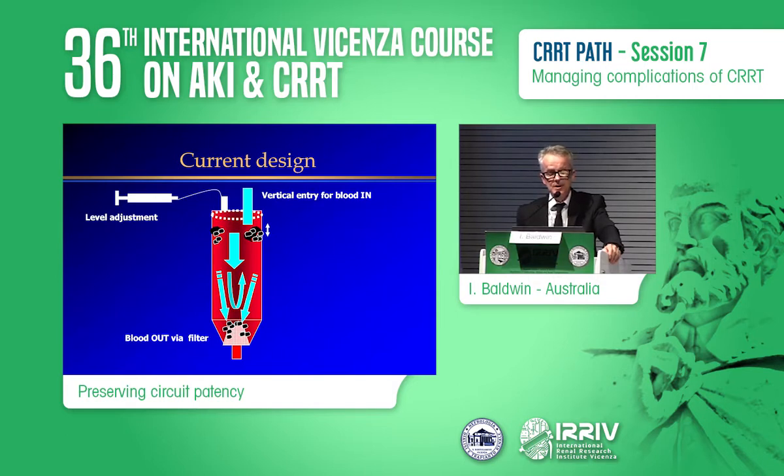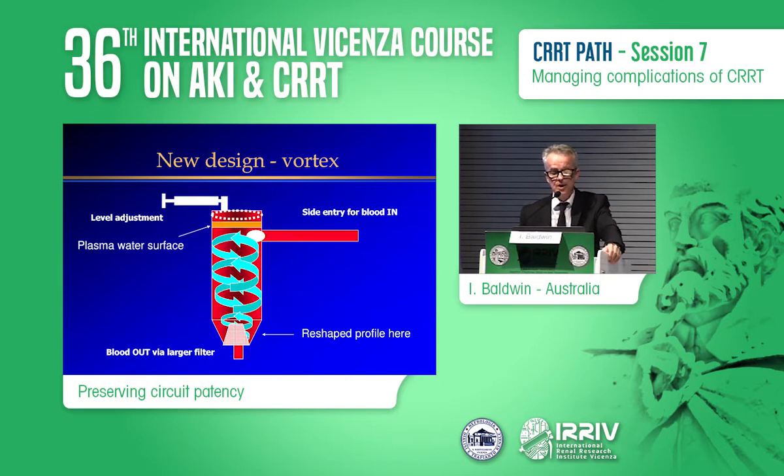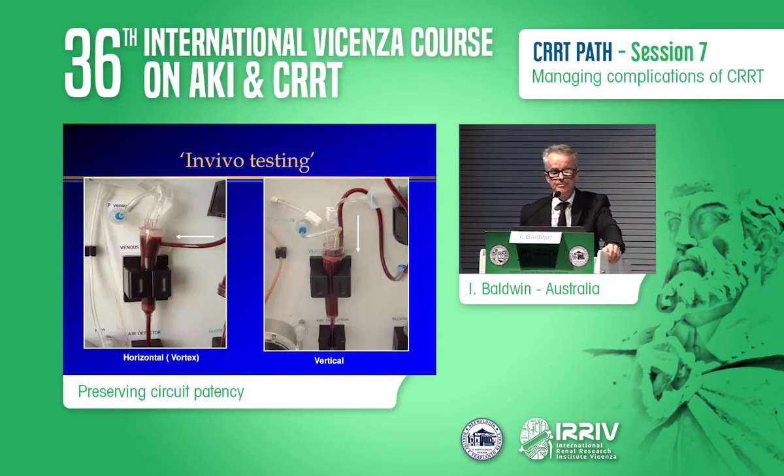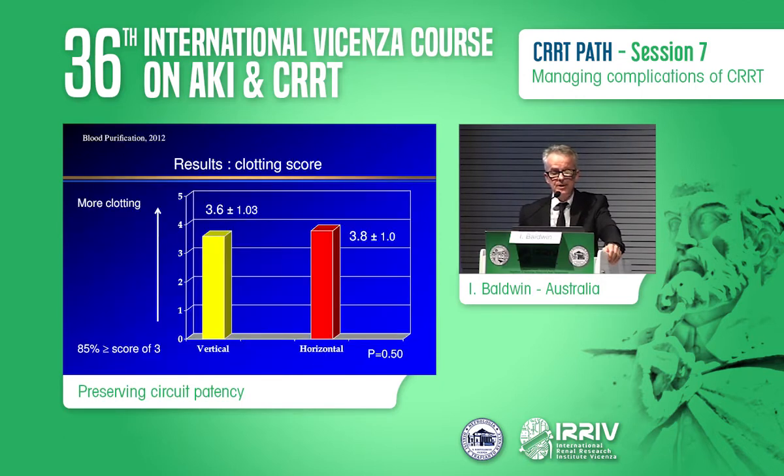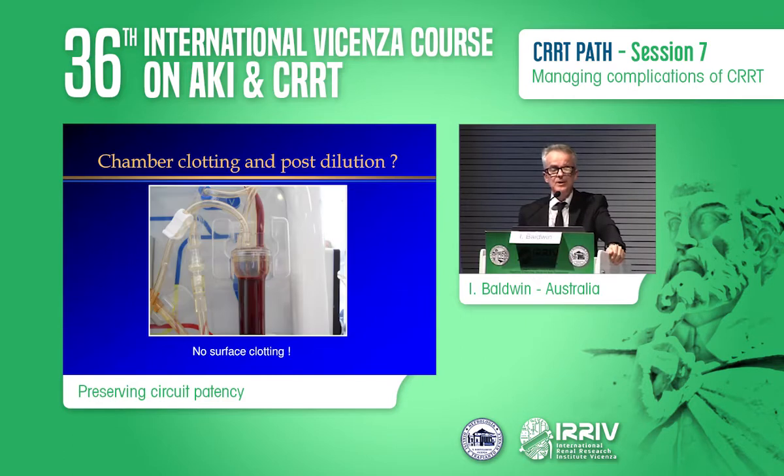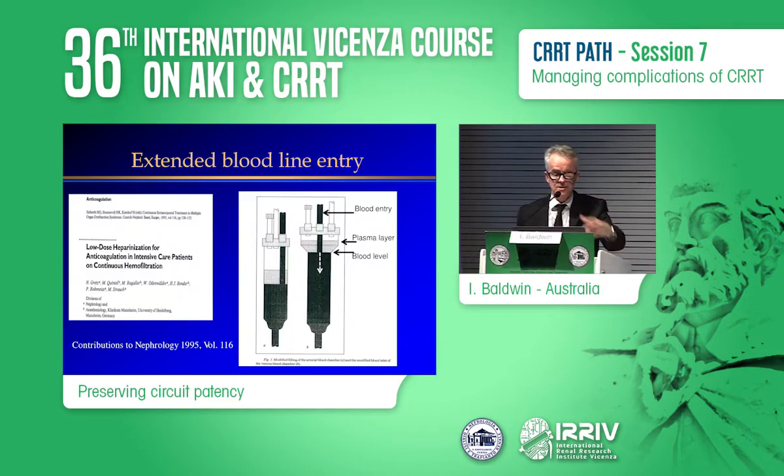And we found this in a small study where I looked at the idea of vertical flow versus horizontal flow. What we noticed in this study was that there is no benefit in vertical or horizontal flow, but we did notice that the post-dilution fluids and the blood do separate very nicely in the air chamber, and you can't easily see the fluid there, but it's sitting on top of the blood and it stops clotting occurring. And it's not something that's new. Back in 1995 I found this research by Gretz and co-workers that in dialysis they noticed there's this plasma layer, which is good news.